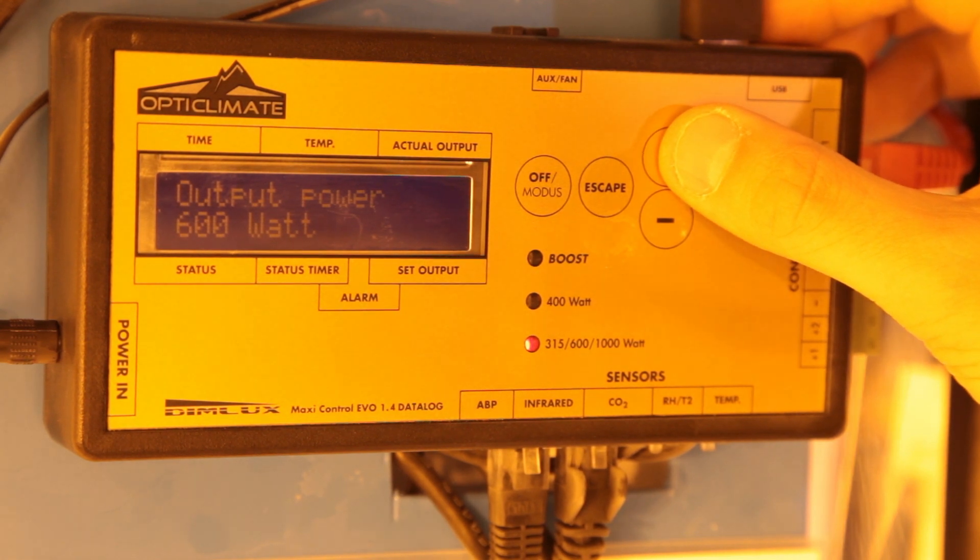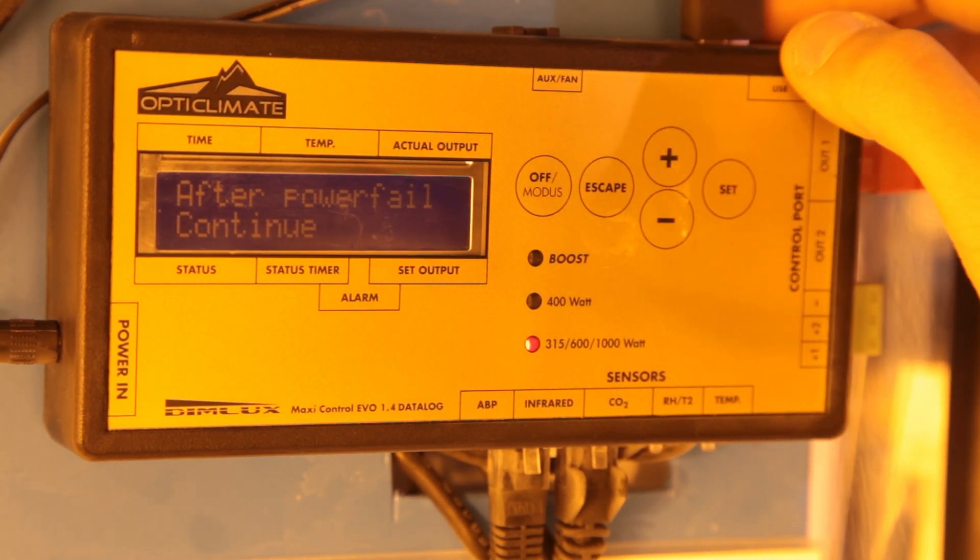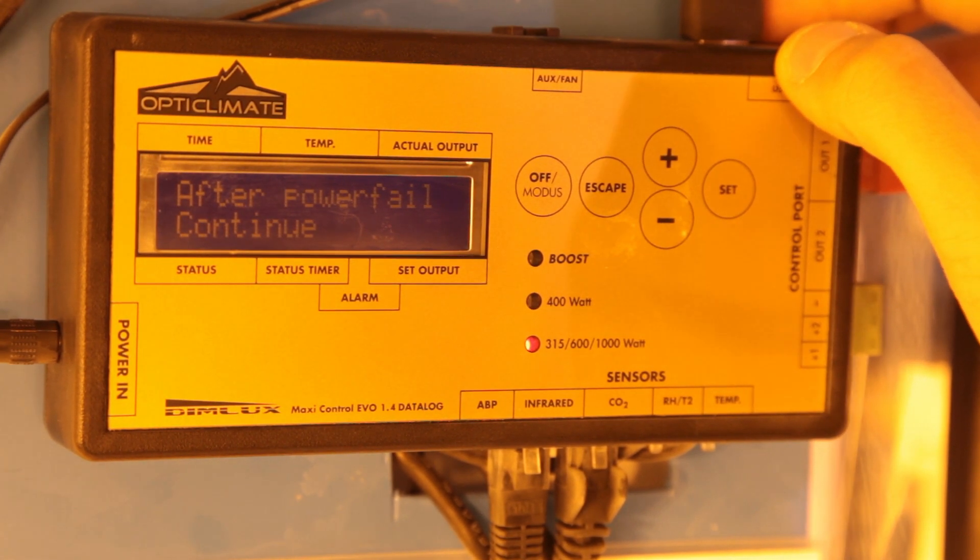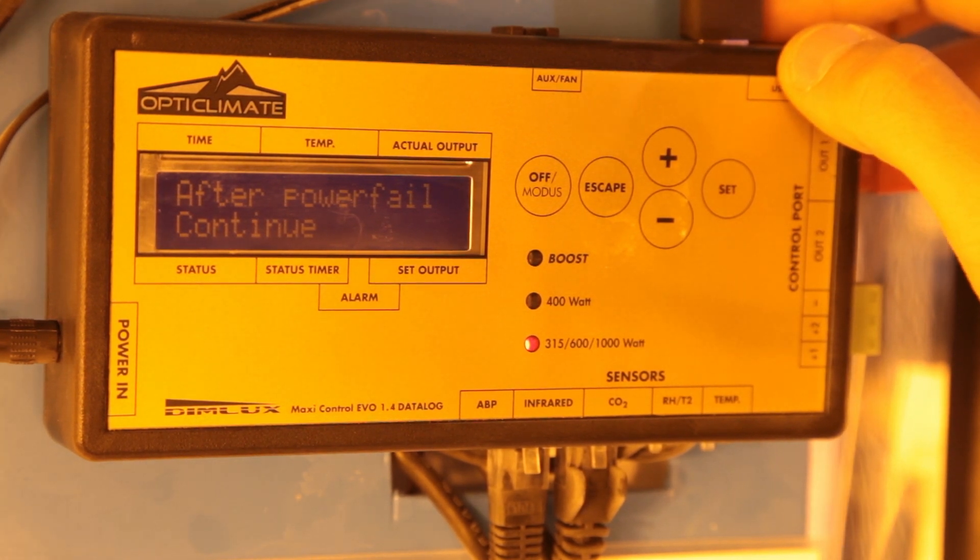Then we've got half phase mode which is for alternating between lights to save 50 percent on energy which can work really well in larger rooms. After power fail it's pretty self-explanatory in that it tells the maxi what to do after a power outage. Generally you want to keep this set to continue so that your lights kick back in automatically.